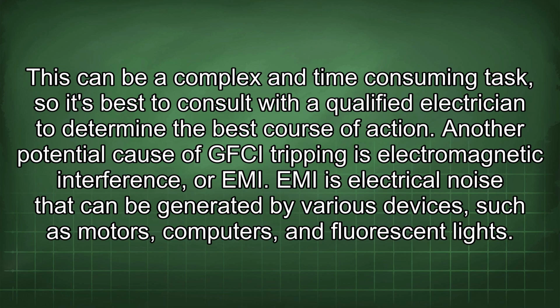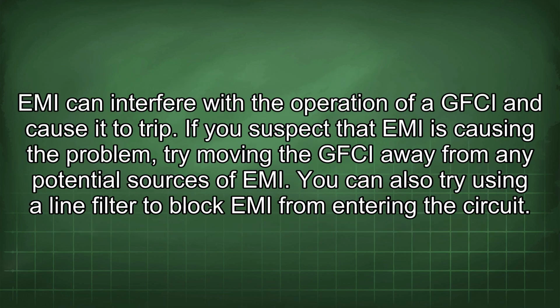best course of action. Another potential cause of GFCI tripping is electromagnetic interference, or EMI. EMI is electrical noise that can be generated by various devices, such as motors, computers, and fluorescent lights. EMI can interfere with the operation of a GFCI and cause it to trip. If you suspect that EMI is causing the problem, try moving the GFCI away from any potential sources of EMI. You can also try using a line filter to block EMI from entering the circuit.